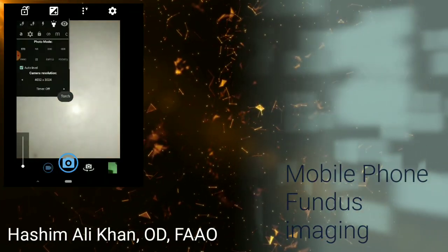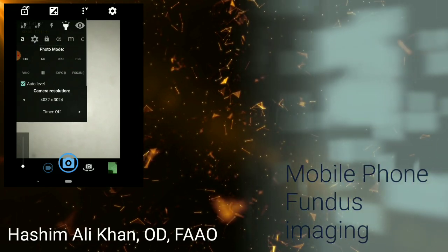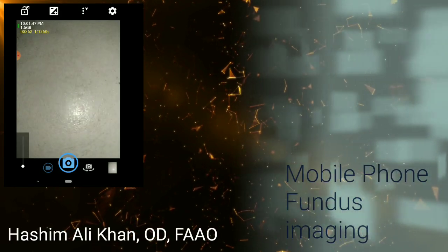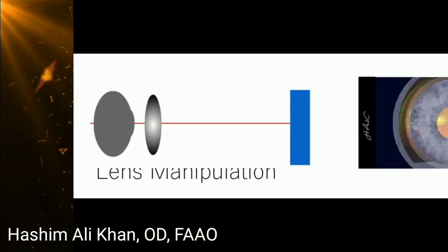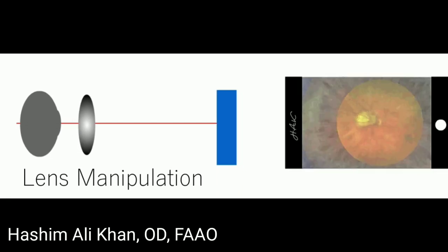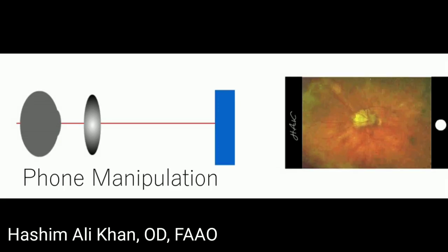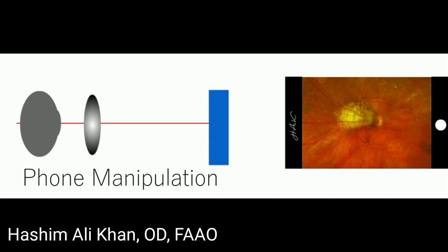Now open the camera, set the flash to continuously firing mode — some call it the torch mode. Adjust the exposure because an overexposed image may be washed out and details are not much clearer. Introduce the lens close to the eye and hold your phone at arm's distance from the lens. Focus the pupil and iris through your camera app. Gently draw the lens away from the eye until the fundus glow fills the entire lens. At this point you can move the phone towards the lens to zoom in, or away from it to zoom out. You can now start shooting and capturing images or movies.